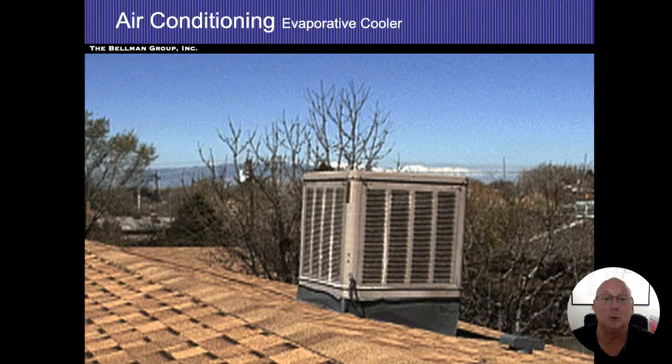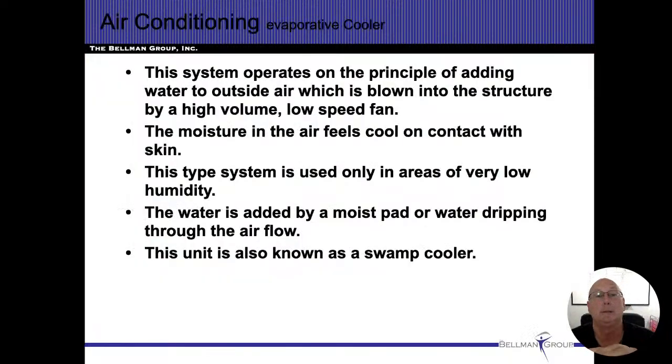So large amounts of air, the windows are open, blow humidity in the house. The humidity lands on the objects. Dry climate causes it to change to a gas. When it changes to a gas, it absorbs the BTUs, and this actually works very well. The system operates on the principle of water and outside air. The moisture feels cool on contact with the skin because it's evaporating. It's only used in very low humidity. Water is added by a moist pad, water dripping, the same type of humidifiers that we use in our own houses. And more of a nickname than anything else, they call them swamp coolers. You'll hear that as well.